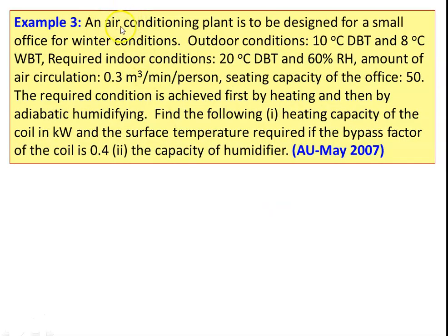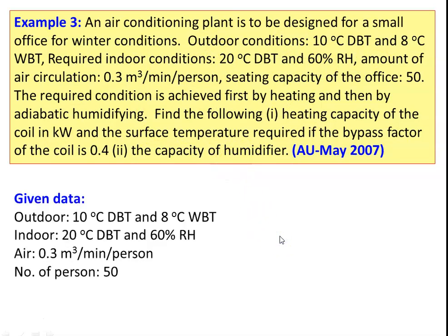Example 3: An air conditioning plant is designed for a small office under winter conditions. Outdoor conditions: 10°C dry bulb temperature and 8°C wet bulb temperature. Required indoor conditions: 20°C dry bulb temperature and 60% relative humidity. Air circulation is 0.3 m³/min per person. The office capacity is 50 persons. The required conditions are achieved by heating and then an adiabatic humidifier. Find: heating capacity of the coil in kW, surface temperature if bypass factor is 0.4, and capacity of the humidifier.